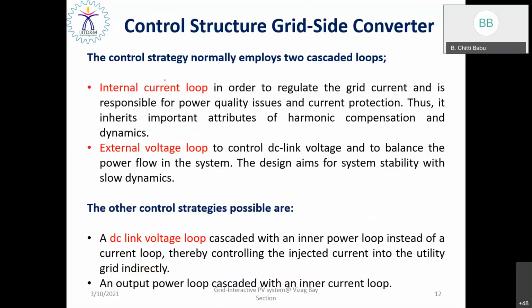Let us come to an important point in the control of the grid side converter. It has to have cascaded control loops. Cascaded control loop means it has an internal current control loop and an external voltage control loop. The internal current control loop is very essential to regulate the grid current in order to provide overcurrent protection to the inverter switches. As all of us know, inverter switches don't have any overload capacity, unlike an induction motor drive. So they have to be protected against overcurrent whenever there is a sudden rise in current.